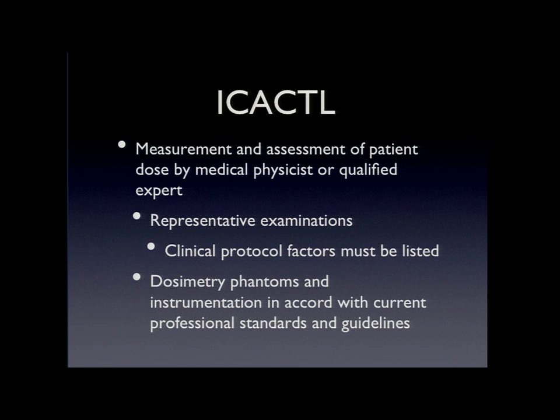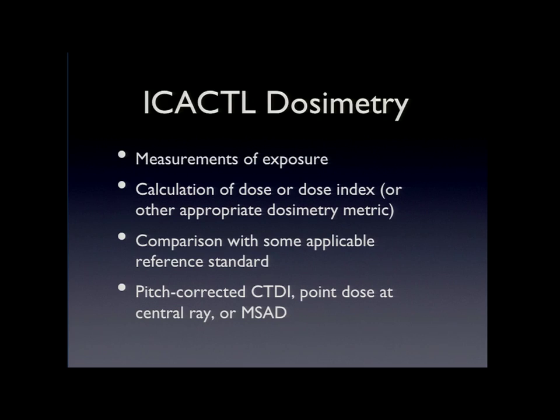Is it CTDI 16, CTDI 32? So we know what we're actually measuring, and use it as a reference, and use the appropriate phantoms and instrumentation, and they should be calibrated. So these are required. You measure these, get the dose indices, and record them.